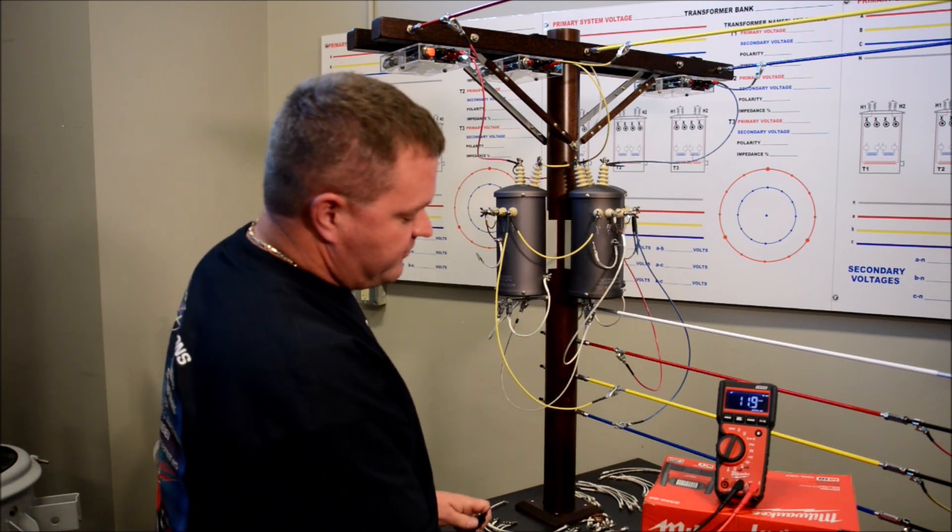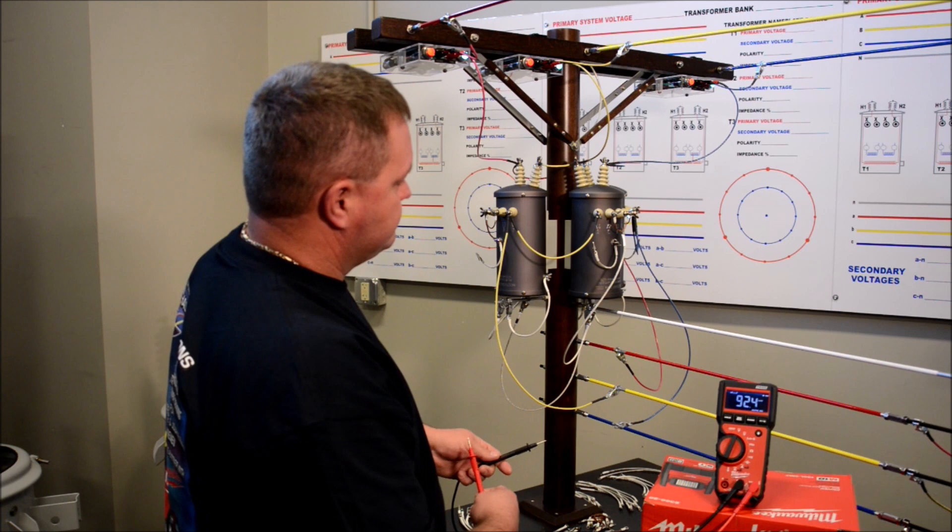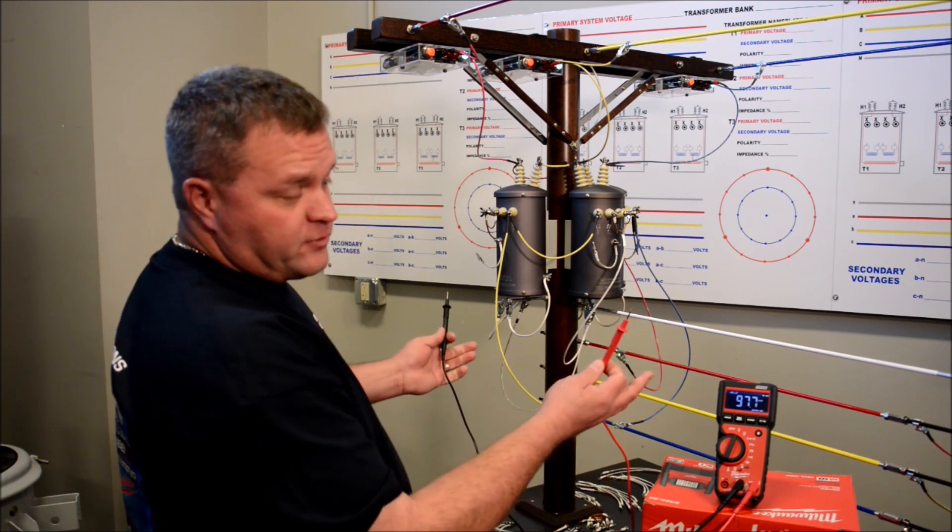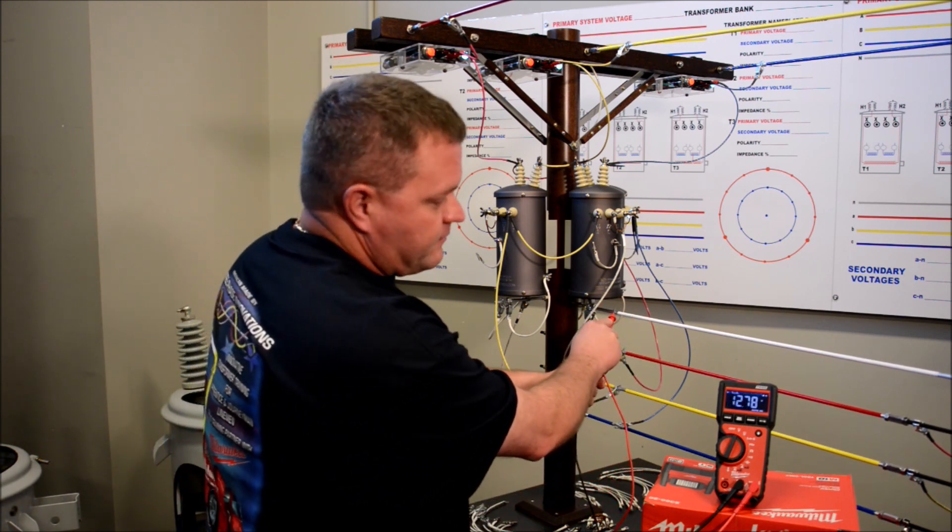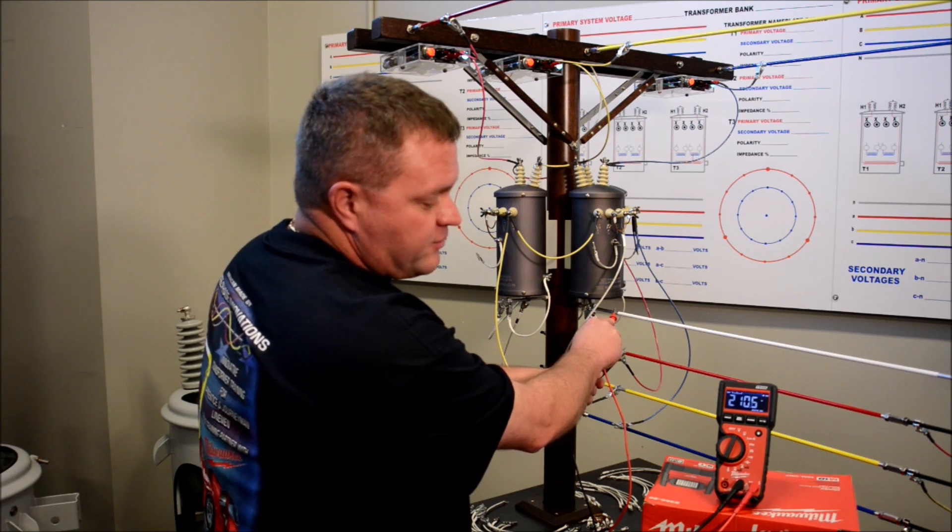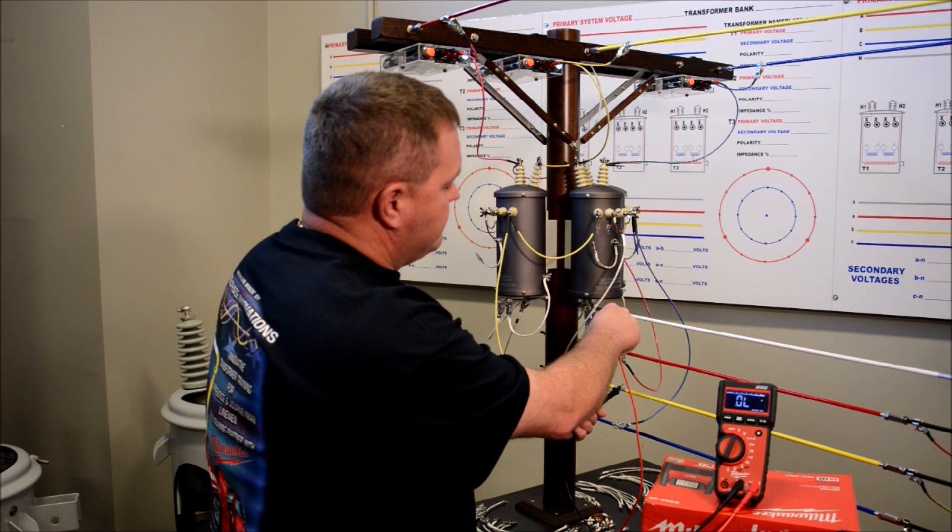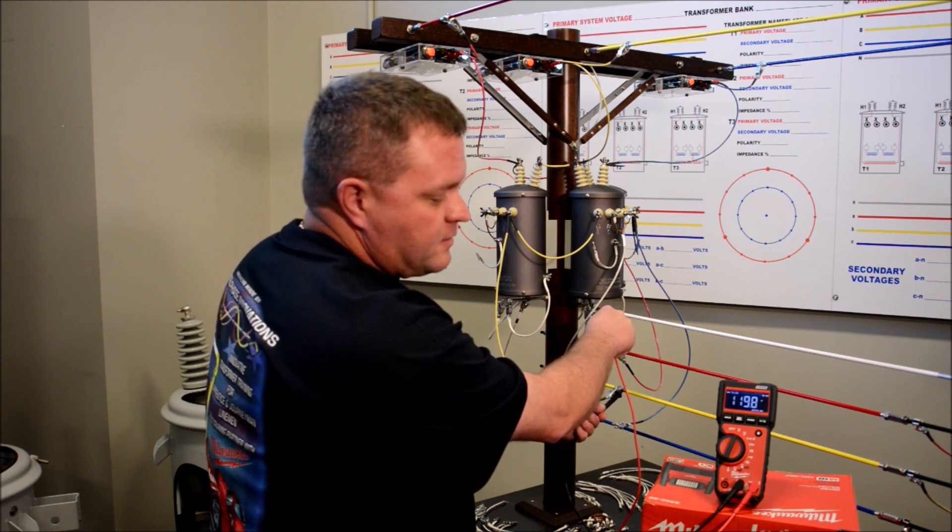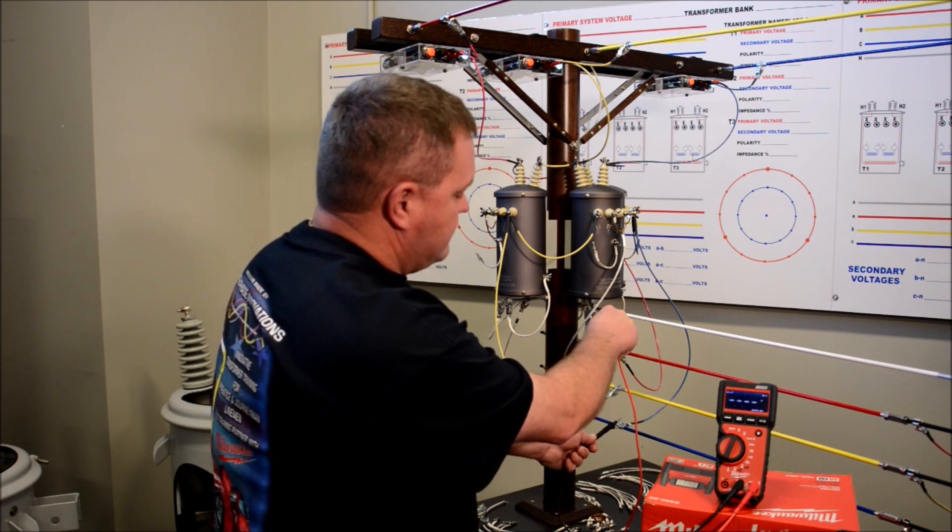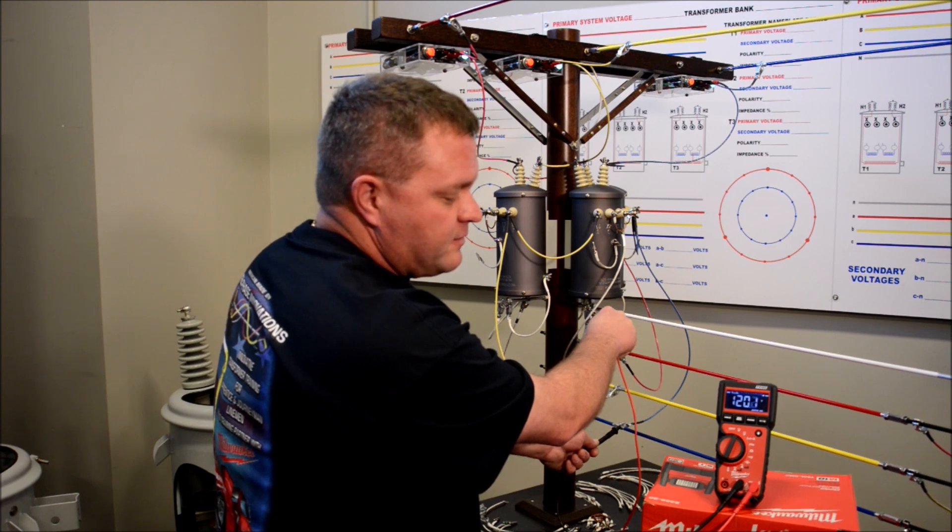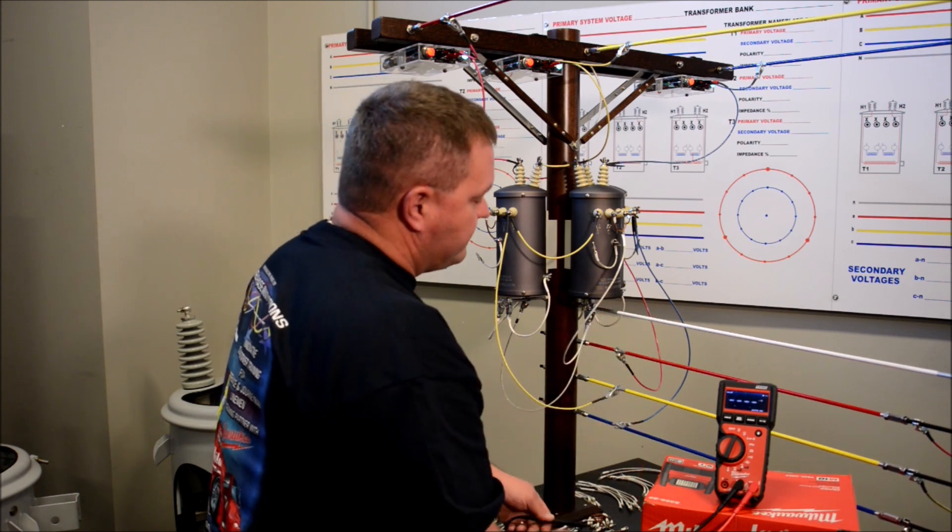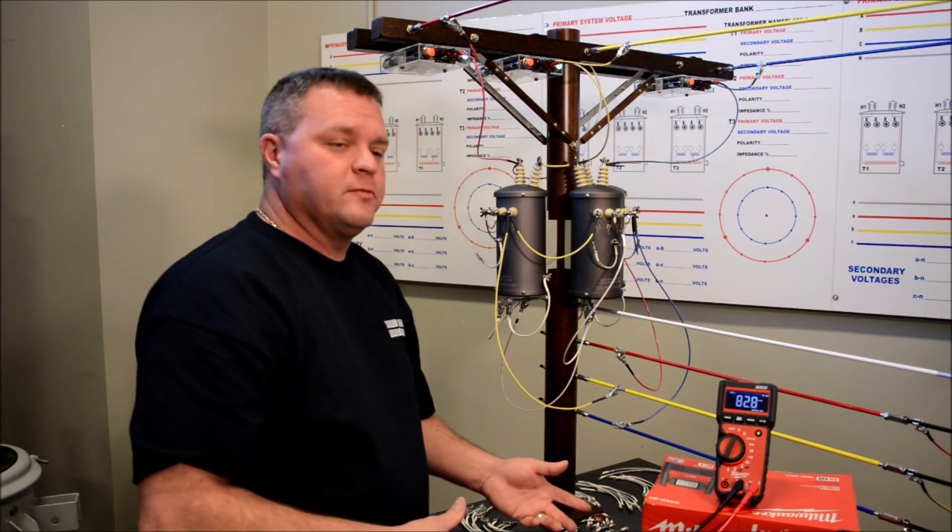Right now we're going to test it. So A was the furthest phase away from the ground, 210 approximately. That's good. B phase 119, C phase 120. These voltages do vary a little bit. These are no-load transformers.